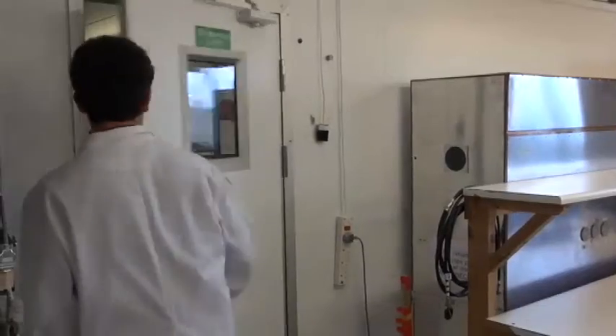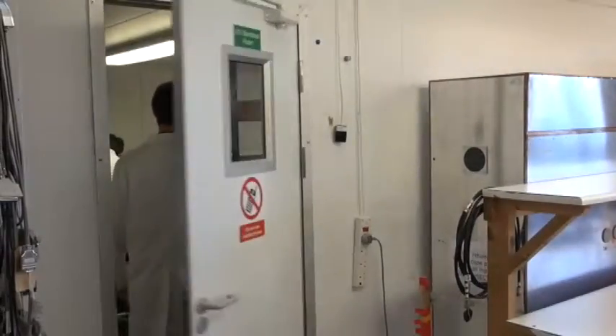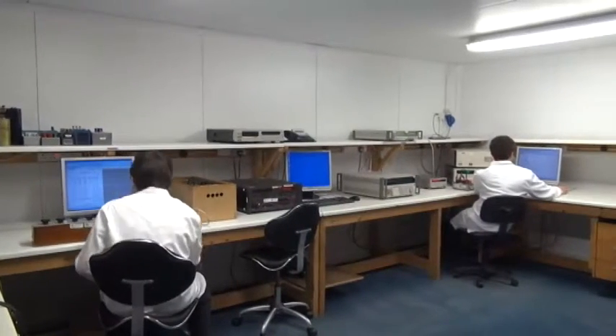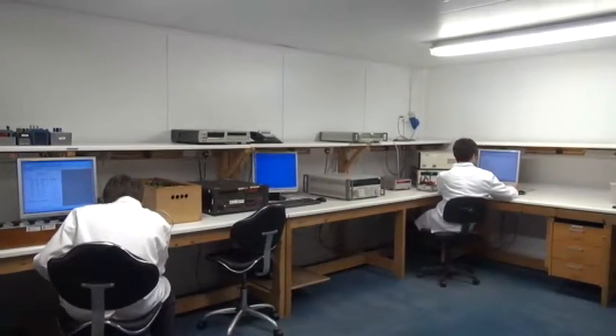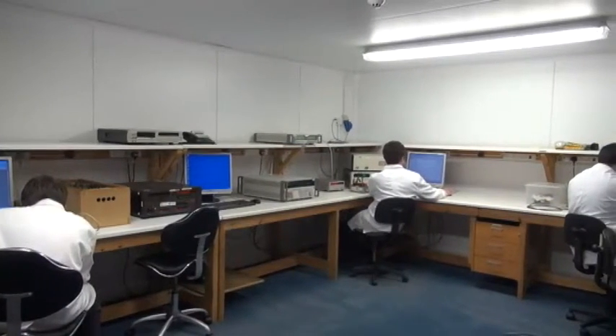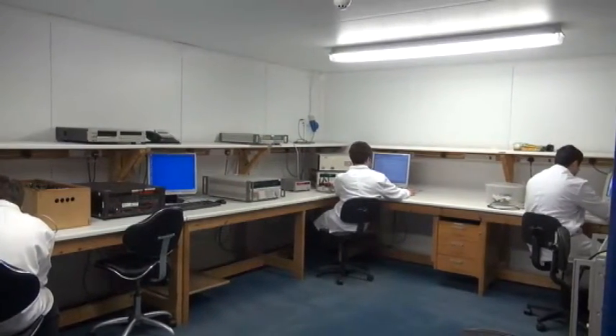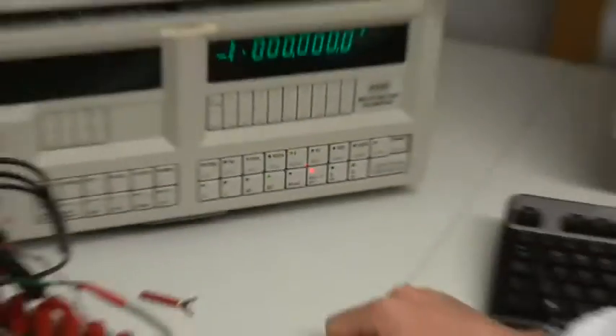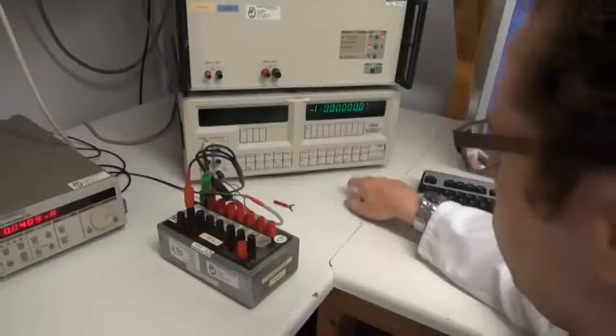We have a specialist direct current and low frequency or DCLF standards room which is temperature and humidity controlled. The more precise equipment is calibrated in here from DC up to around 100 kilohertz AC. The measurements made in our DCLF standards room have uncertainties of parts per million and are highly precise.